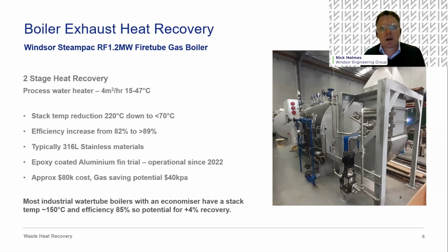This one was a little bit special. It was a bit of an R&D opportunity to use some slightly cheaper materials. Typically, when you're condensing, you need to use stainless steel 316 to minimize the corrosion effects of the condensing flue gases in that stream. But we actually used, in part, an epoxy coated aluminium. Aluminium has the benefit of being a much better heat transfer material, but it is more susceptible to corrosion. This trial's been going 3 years and it's held up well. So it's giving us some comfort that we have a lower cost solution for the longer term that can be put into the market.